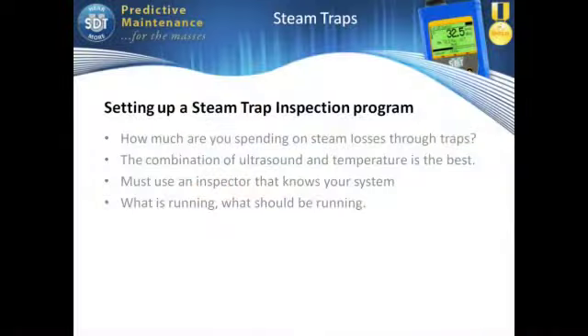Don't send a boy out to do a man's job. Definitely the case when it comes to inspecting steam systems. It's very, very important that your inspector knows the steam system. You have a cold section. Is it cold because it's not in operation, or is it cold because you have a blocked steam trap? You need an inspector that knows the system to be able to tell the difference. In other words, to know what is running versus what should be running.